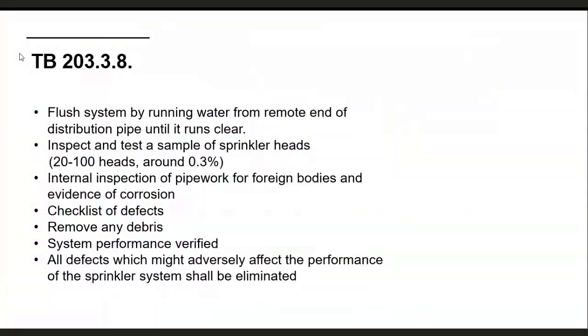So looking in a bit more detail, what do you actually have to do as part of the 25-year inspection? First of all, flush the system by running water from the remote end of the distribution pipe until it runs clear. So we're going to be doing some flushing through the pipework - the sprinkler system will be connected to a water supply.